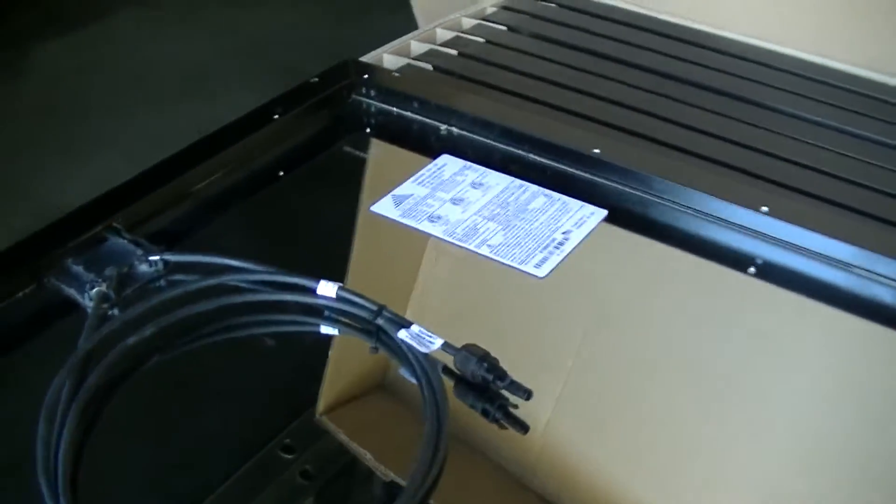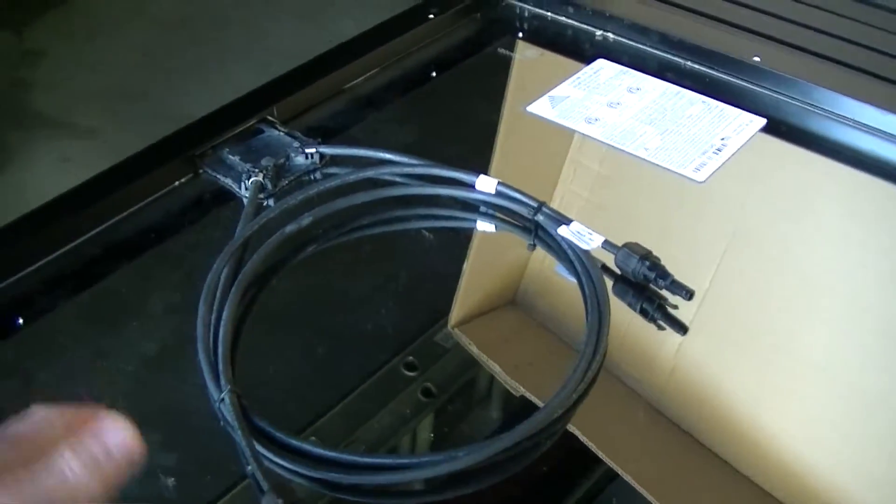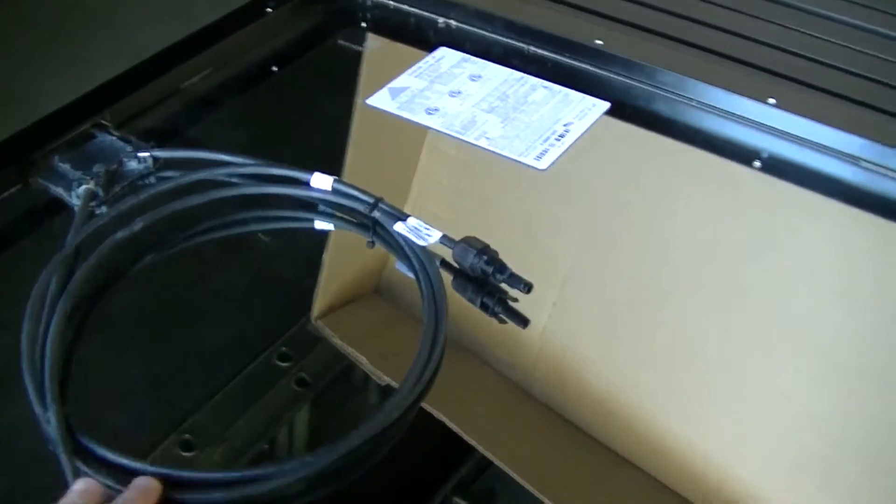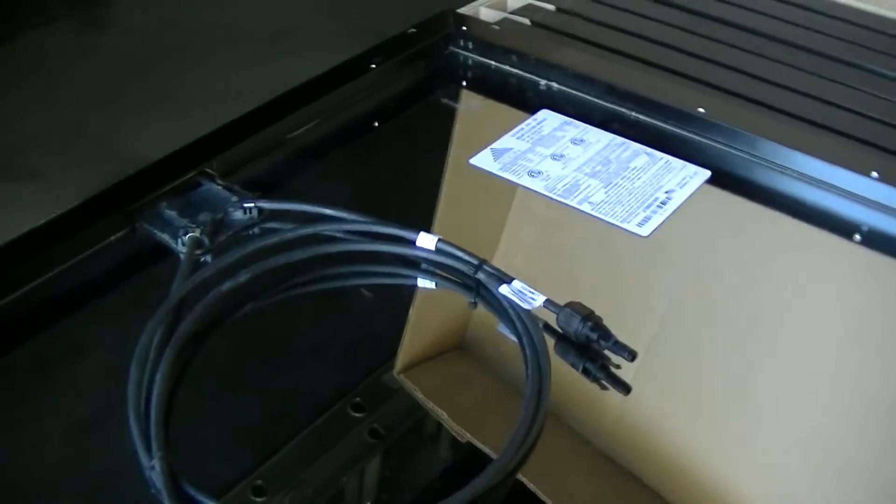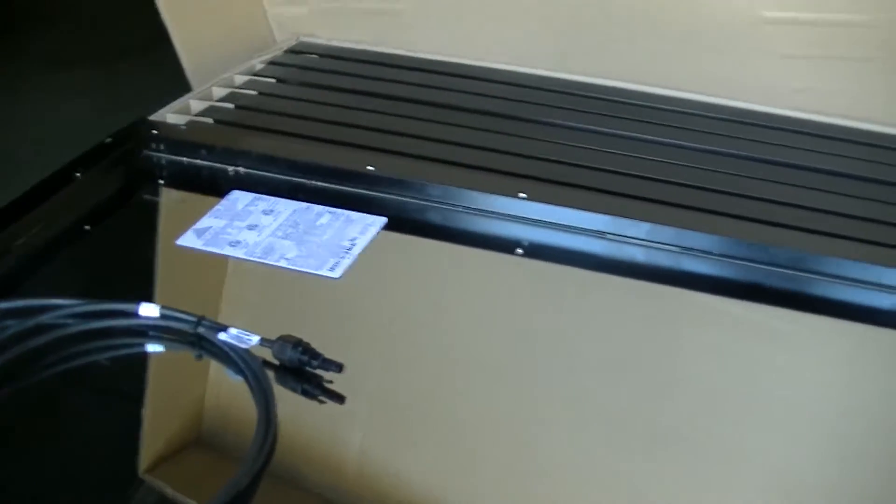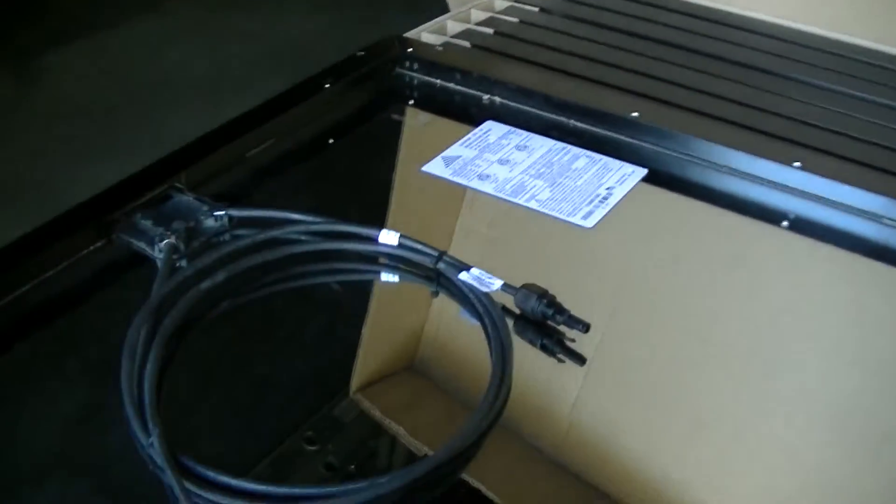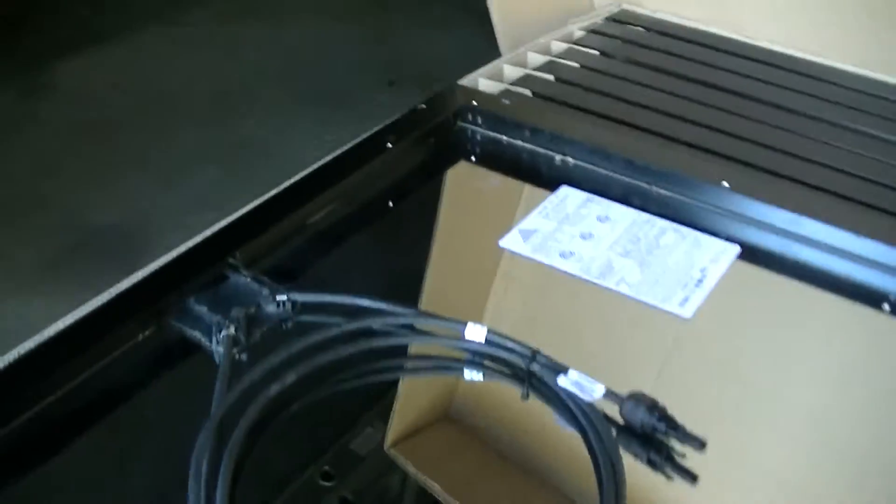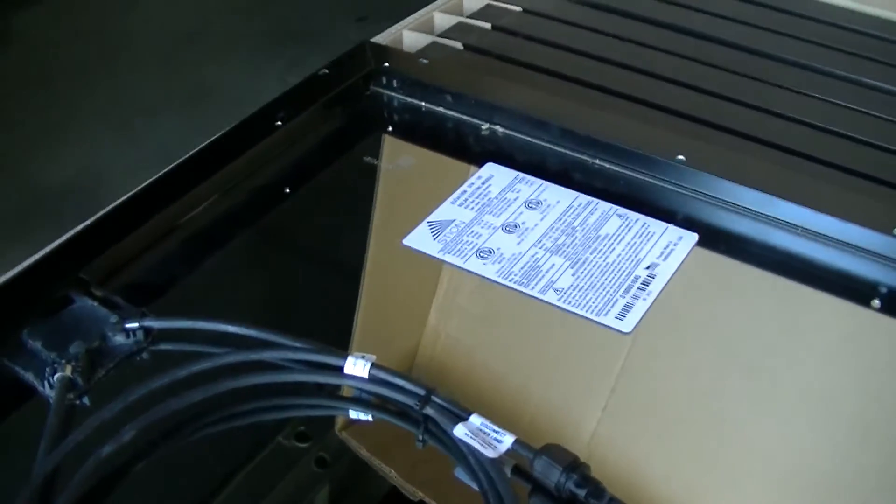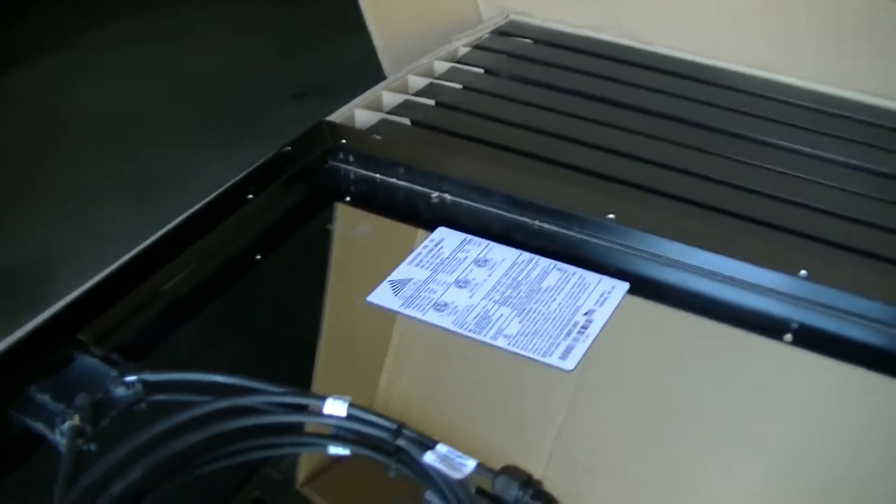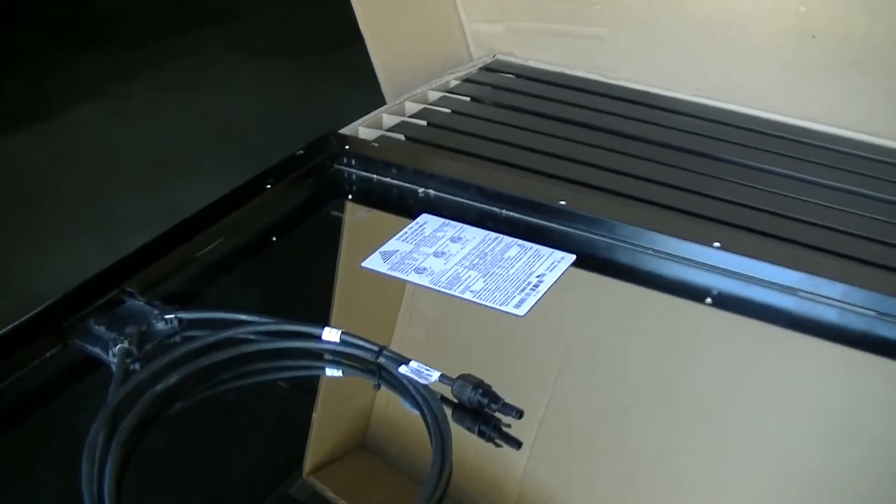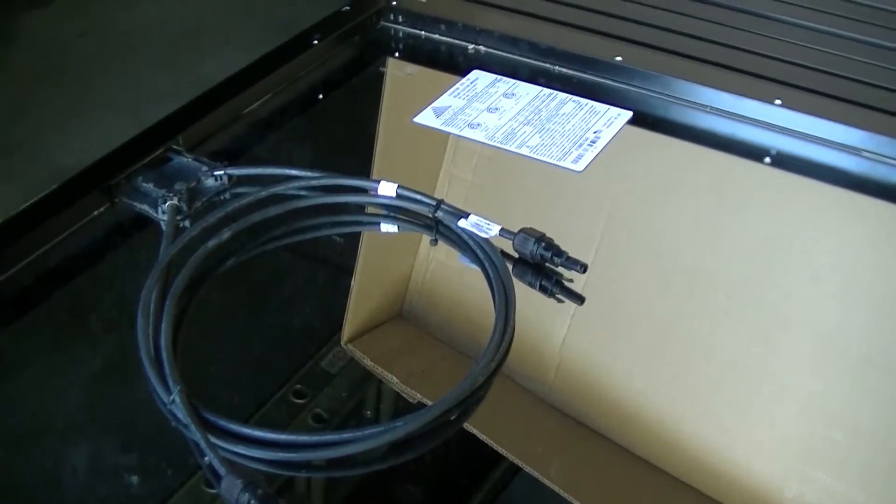But if you connect them, if you went with something else like an outback inverter which uses 48 volts, you'd have to connect these all in parallel, and 25 of these at 3 amps, that's going to be a lot of current, and you'd have to have big wires to handle all that current and you'd have a lot of loss. So we want the high voltage DC. And then also with the transformer-less model of the SMA inverters, there's actually an emergency feature.